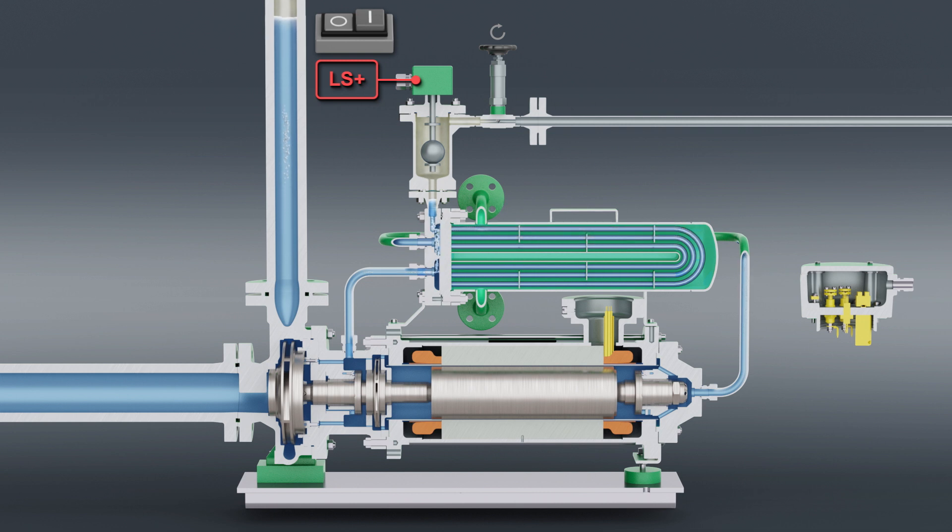The air of any potential air cushion in the rear motor compartment or in the vicinity of the impellers and sleeve bearings is displaced and removed during or shortly after the filling process through the pressure pipe and the air bleed valve, which is closed subsequently.